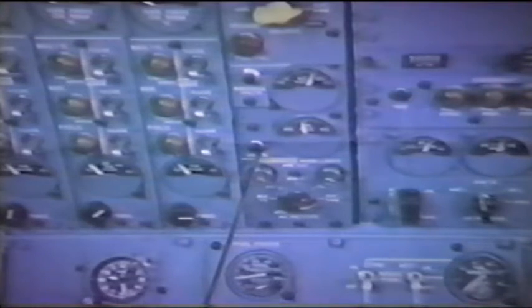Also, while we're looking at this portion of the electrical panel, I just want to mention that we do have an AC voltmeter and frequency meter here. And we have a kVAR button, which is not normally used, but when pressed, it allows the kilovolt ampere reactive, the internal losses to magnetizing coils, things such as that, to be reflected on your kW meters for each individual generator. And the residual volts button is used to measure the residual volts for each generator.